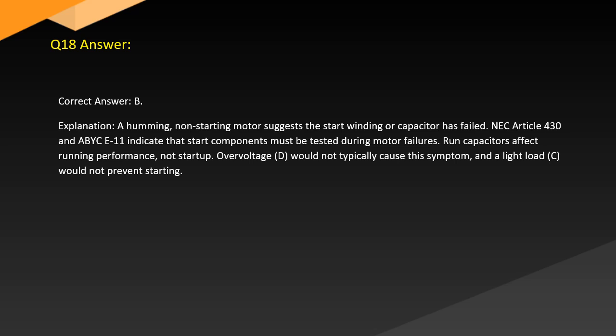Answer. Correct answer: B. Explanation: A humming, non-starting motor suggests the start winding or capacitor has failed. NEC Article 430 and ABYC E-11 indicate that start components must be tested during motor failures. Run capacitors affect running performance, not startup. Overvoltage (D) would not typically cause this symptom, and a light load (C) would not prevent starting.